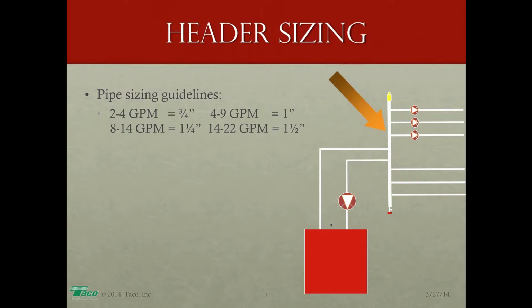And we simply do that by knowing the BTU load we're trying to deliver. We know the delta T to which we are designing, and we simply do the universal hydronics formula: GPM equals BTUH divided by the product of delta T times 500, if we're using 100% water. So let's say we have a system where we have to deliver 80,000 BTUs at a 20-degree delta T. 80,000 BTUs divided by 20 times 500, or 10,000, would be a delivery flow rate of 8 gallons per minute. So judging by these guidelines, we're looking at 1 inch copper pipe.